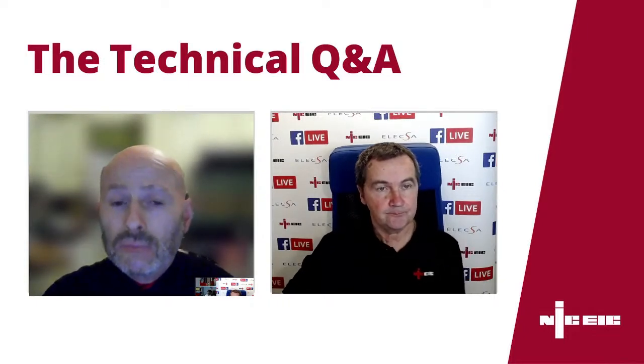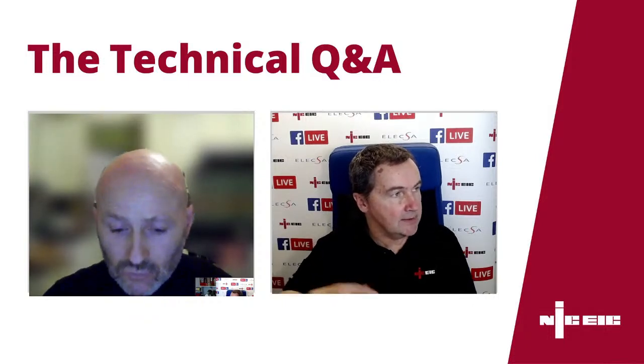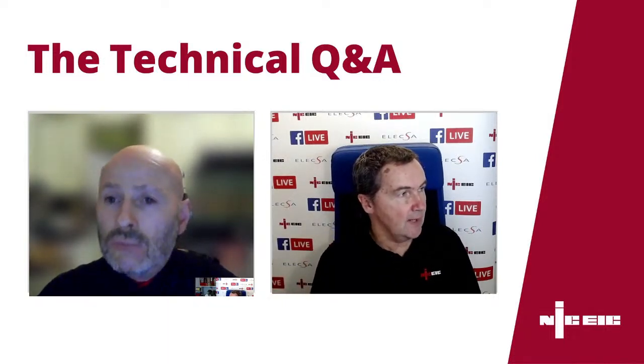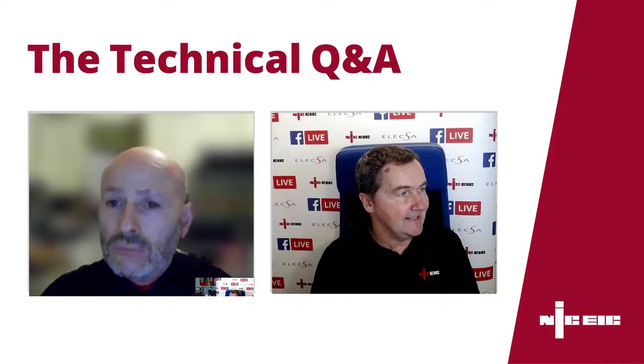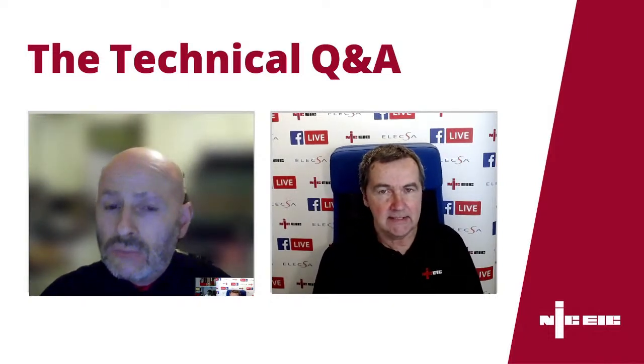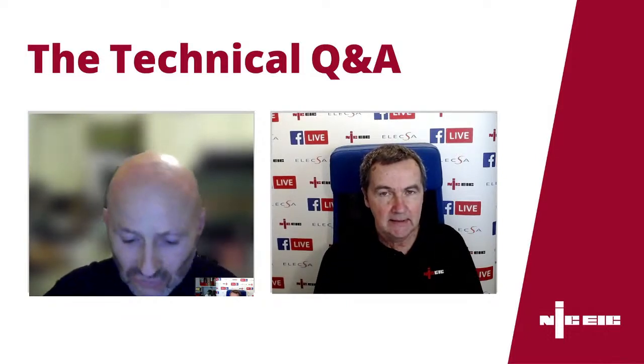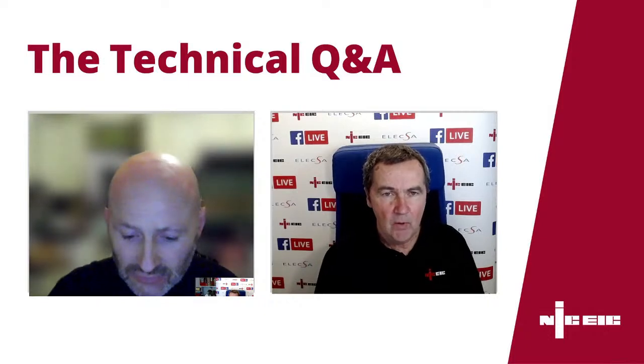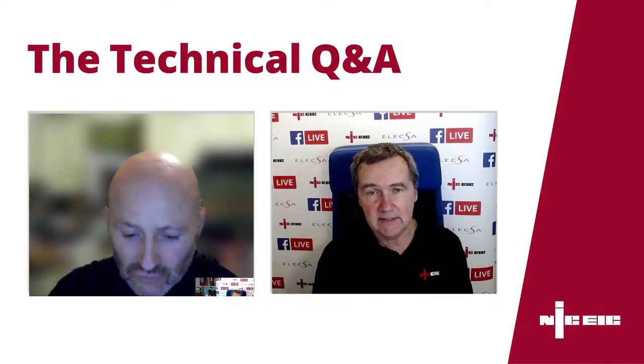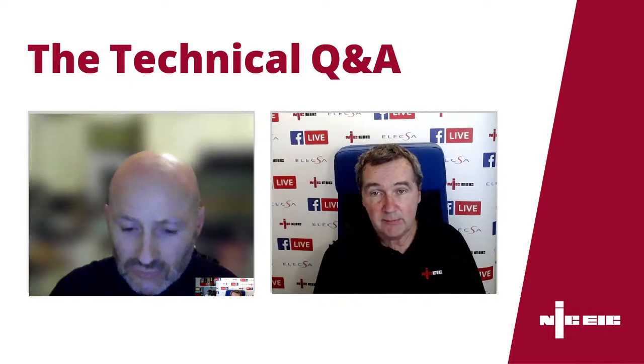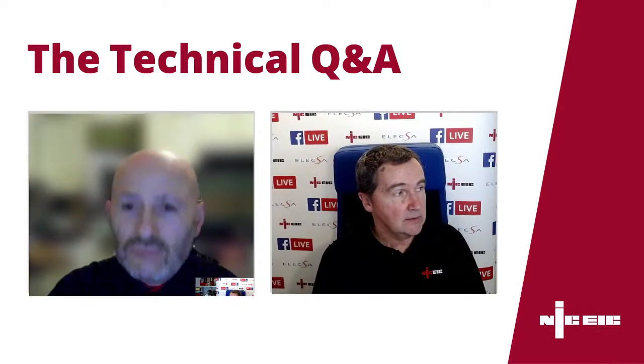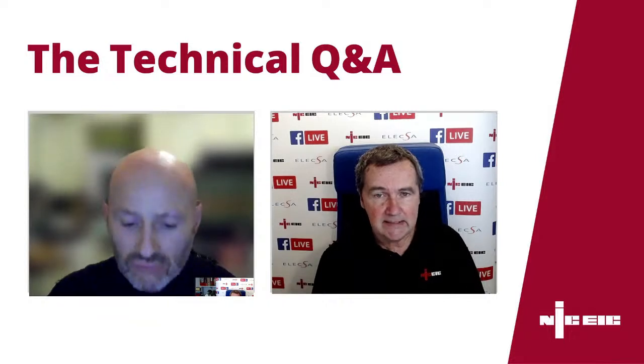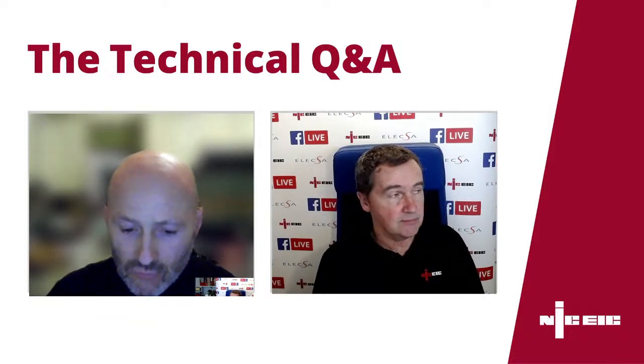Yeah, spot on. Okay, looking at the questions that are coming in on the chat so far. So the first one was, what code for an AC RCD on an EICR? So we're aware now in BS 7671 that it clearly states that AC type RCDs should only be used on fixed equipment where it's clear that there's no evidence of DC components being produced by the load. So it would straight away be considered as non-compliant in those situations for an AC.